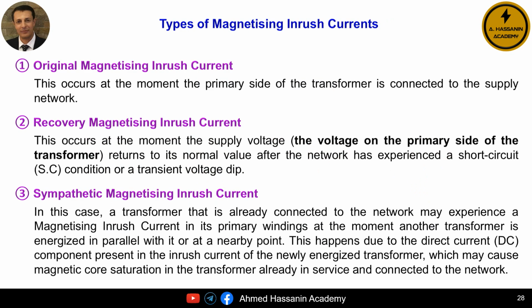Therefore, we can say that there are 3 types of magnetizing inrush currents. The first type is the original magnetizing inrush current, which we are all familiar with, and which occurs at the moment the transformer is energized and connected to the network. The second type is the recovery magnetizing inrush current, which occurs when a transformer is unintentionally de-energized and then re-energized in a very short time due to transient events on the power system.